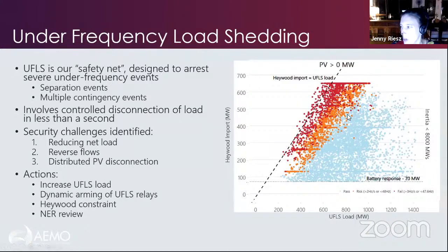So we also have a very large program of work underway to restore these safety nets. We're increasing the amount of load that's on our under-frequency load shedding scheme as a short-term stopgap measure. We're also looking at dynamic arming of UFLS relays. So that would have the relays be much more intelligent and able to detect when the relay circuit is in reverse flows, and it would disarm that circuit. That doesn't bring back the load, but it does mean at least we're not tripping circuits that are exacerbating the disturbance. We've also put in place some constraints on our Heywood interconnector so that we will ramp it down when we're in periods where we know that we're at high risk with a lot of PV operating.